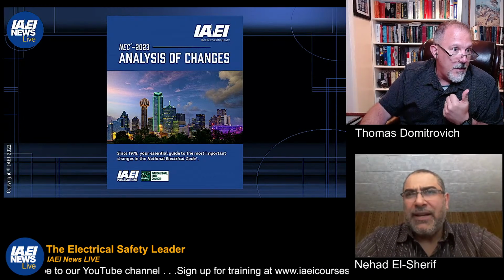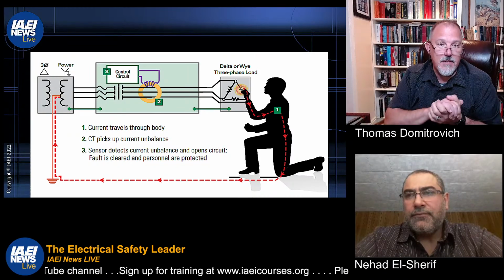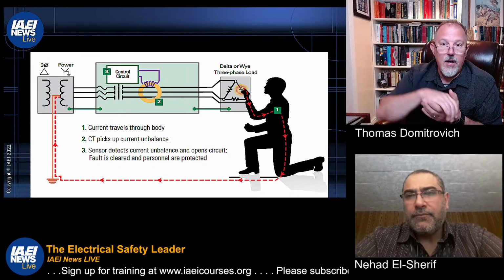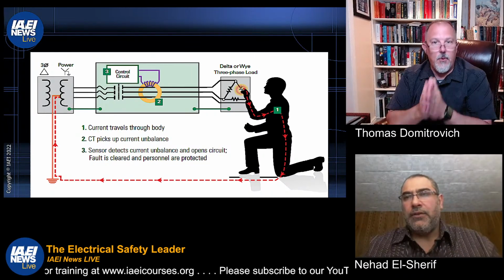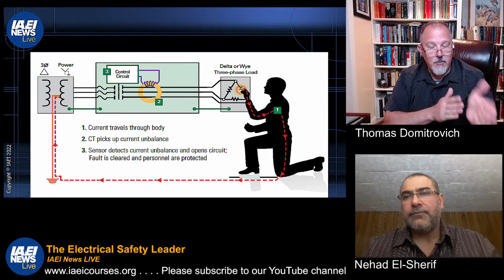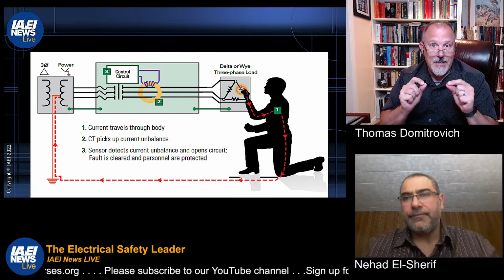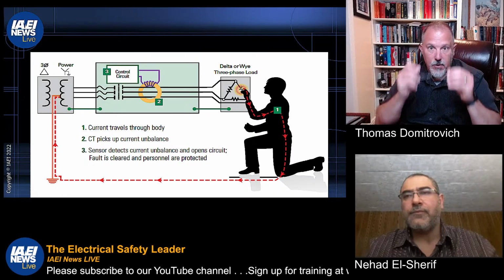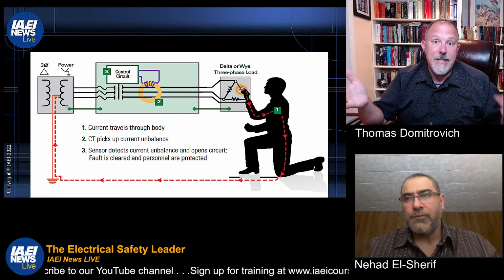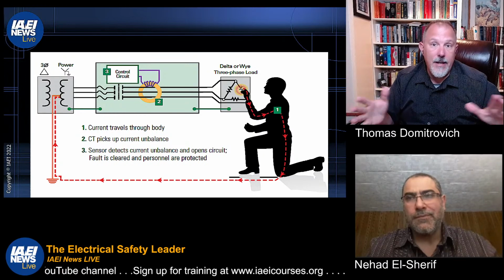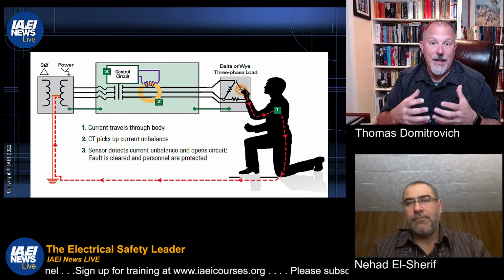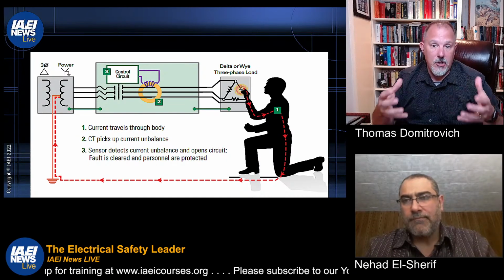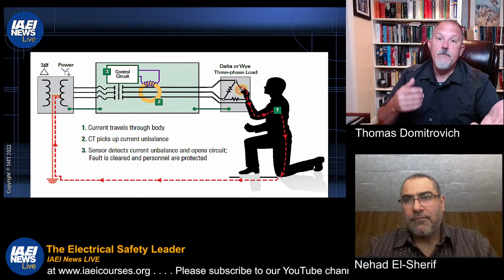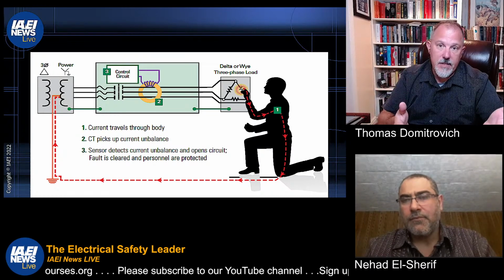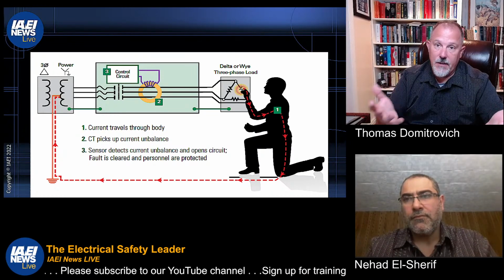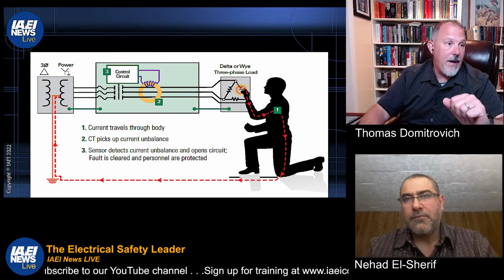All right. So where do you want to go next, Nehad? I'm not sure what's the next slide, but I guess you want to go to the three-phase? We already talked about the single phase. This is the three-phase example of current flowing through the body. I think your point here, regardless of whether it's three-phase or single phase, is that currents will take all paths back to the source. You could have a grounded system, you can have very good bonding going on. That's not going to stop current from passing through your body. You have an energized enclosure, whatever that load is. If it doesn't clear that overcurrent protective device and it stays energized because the current values are low enough, then it can pass through your body.